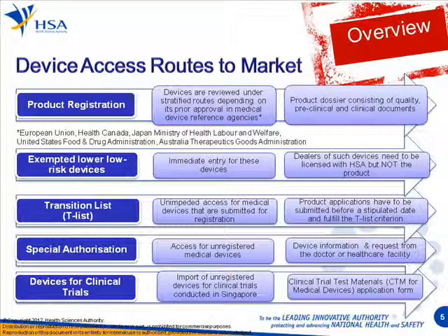Okay, likewise, we also have the exempted lower risk medical devices. This is in reference to the Class A exempted devices. What's happening now is they are exempted from product registration, so they'll have immediate entry to the market. But what is the catch here is the product doesn't need product registration, but the dealers dealing with Class A non-sterile devices, you have to be licensed in order for you to perform these activities.